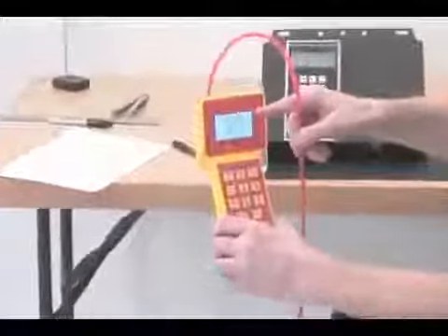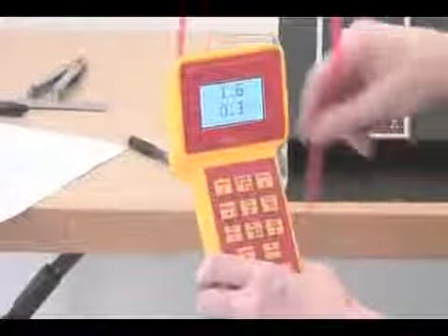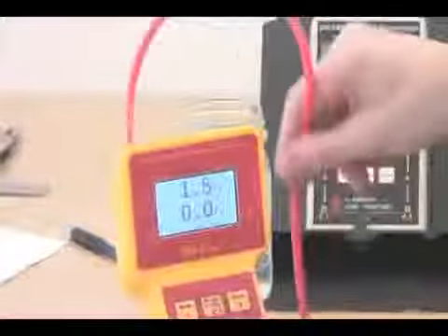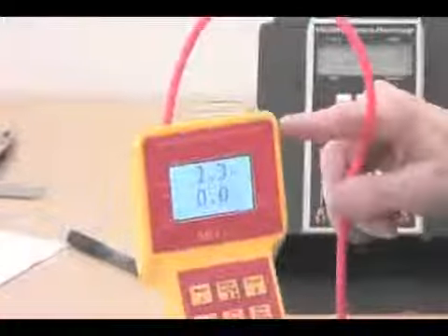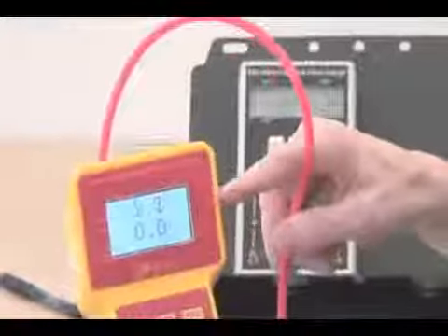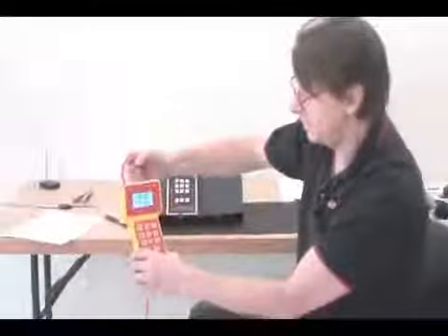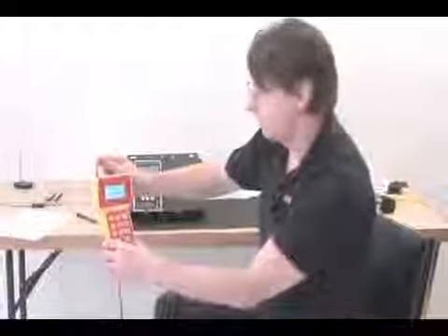So all we do is we take this tube and we move it around, and you'll notice on the display here that it's changing quite a bit. It's changing as much as 2 pascals just by moving the tube around. And this is something that might occur if your tube was outside and was elevated and the wind was actually moving your tube around, or the tube was, say, somehow unsupported. You definitely don't want this kind of thing, so your tube must be secure.